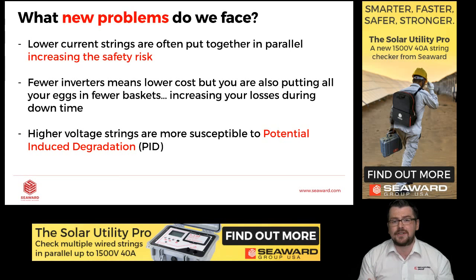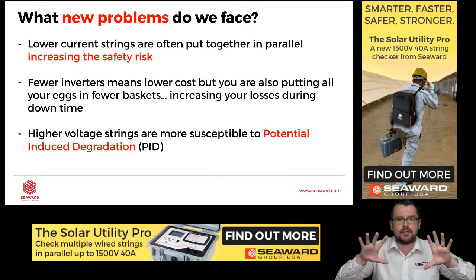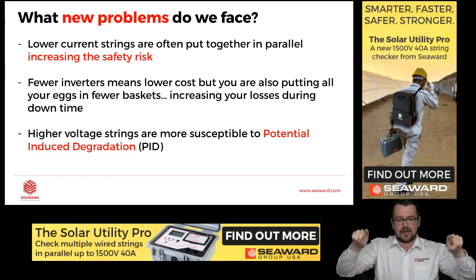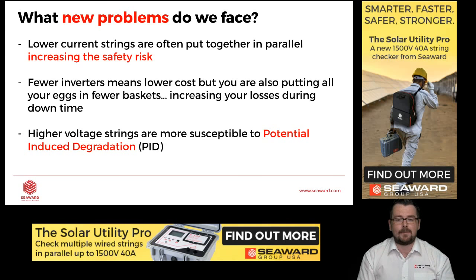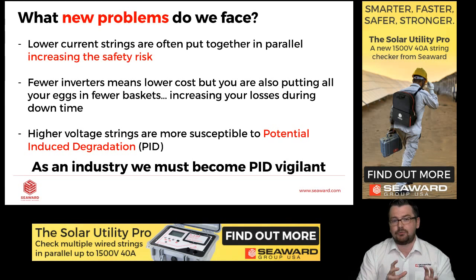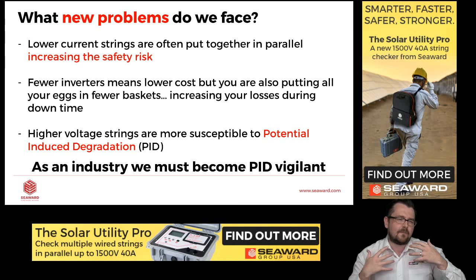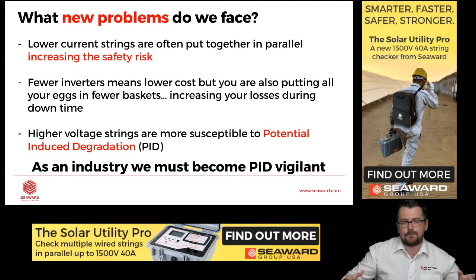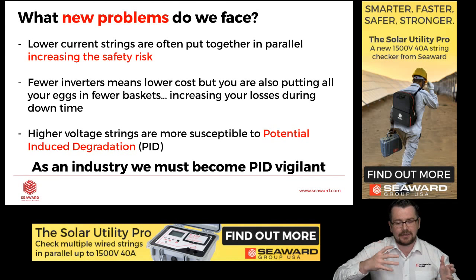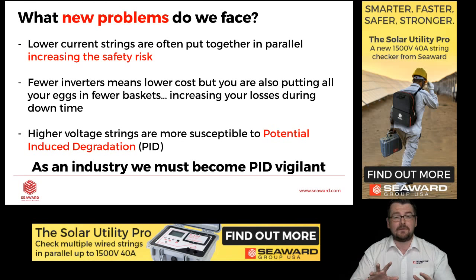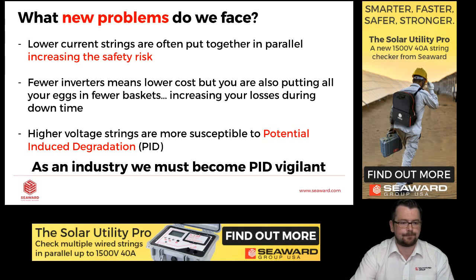Also, higher voltage strings are more susceptible to PID, potential induced degradation. Just very briefly on this concept, this is when the voltage within the solar panel is trying to escape into the metal mounting frame, the frame of the panel, and also to the back sheet. And this degrades the silicon over time, and we call this potential induced degradation. So, as an industry, we really must become more PID vigilant and look out more for PID, particularly on 1500V systems that have been installed for a longer period. So right now, it might not be so apparent, but during the life cycle of that system, PID, I think, is going to be very much more apparent than in 1000V systems.